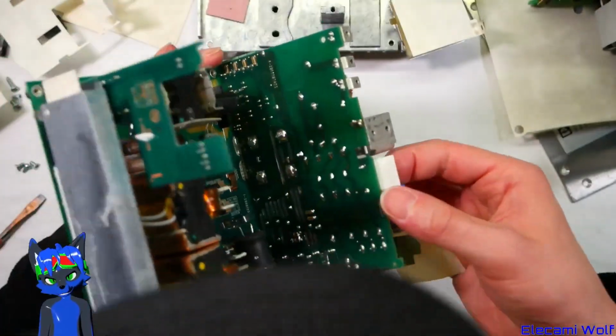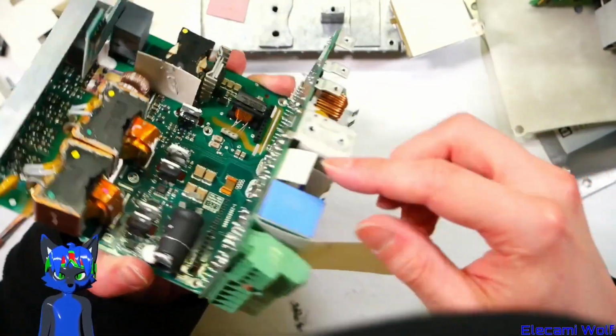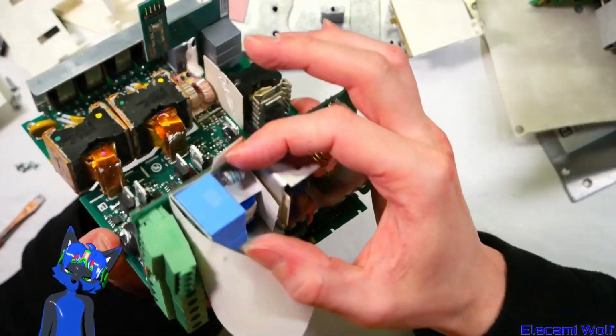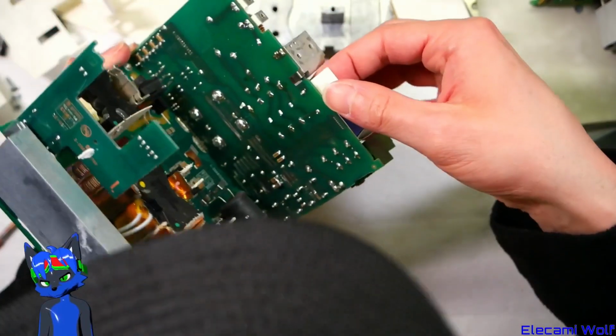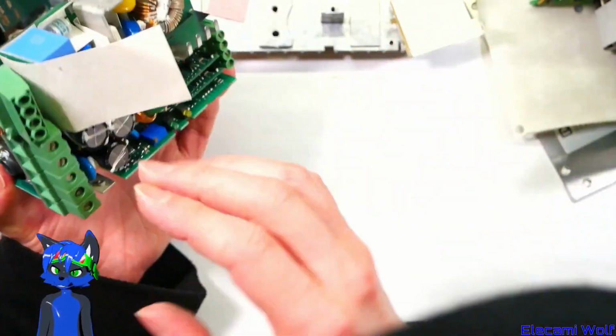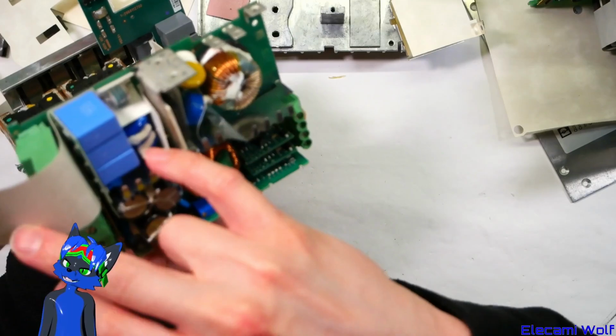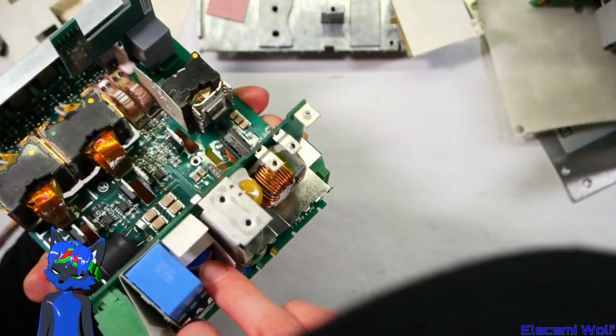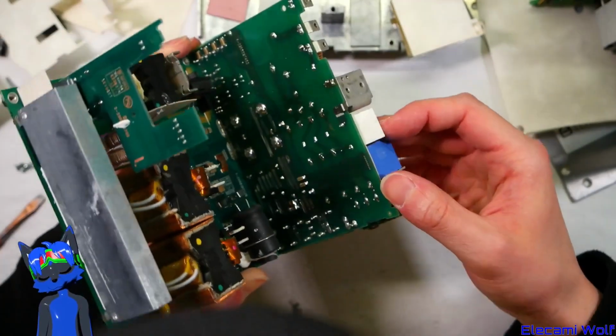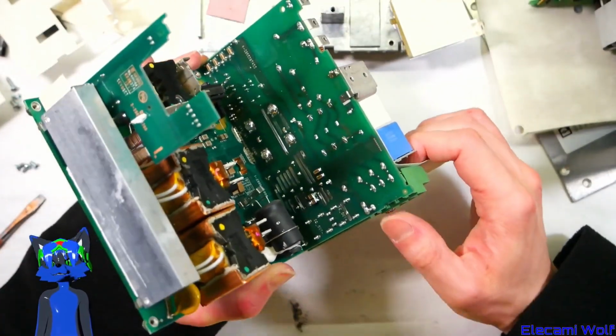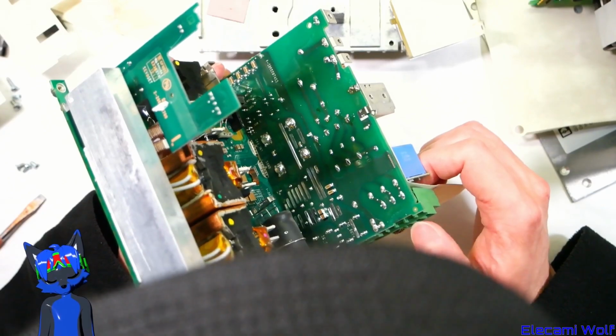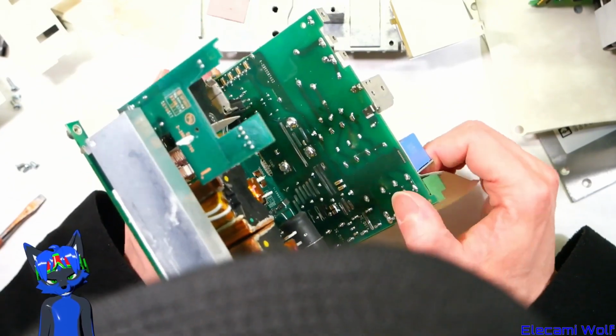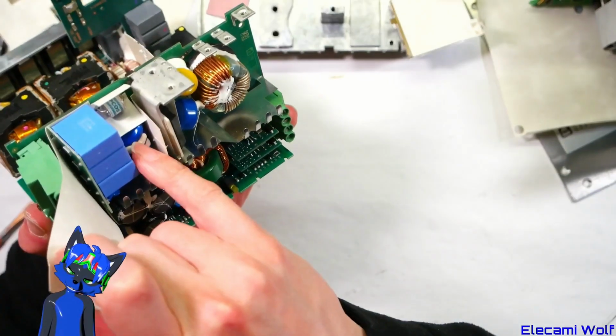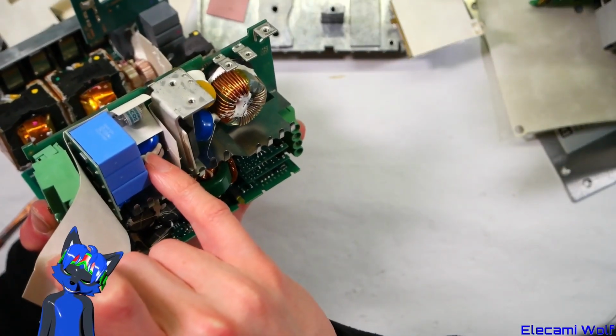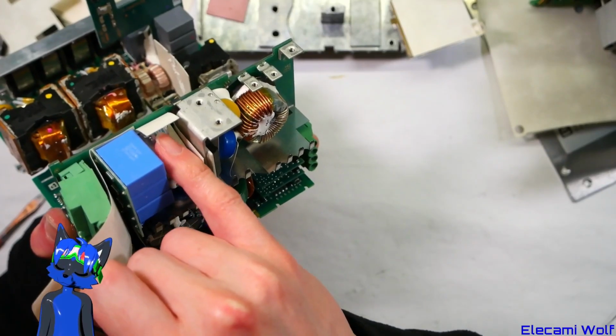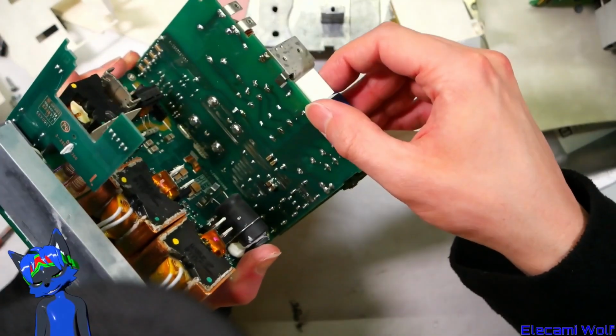Then there's a gas discharge tube, a gas arrestor - one of those, off the star point of 3 VDRs there. Those will be VDRs, and that goes to ground. So that's for surge arresting, like lightning strikes. Surges on the incoming supply cause the VDRs to start conducting, and then break down that gap in the tube, which suppresses it down to ground.